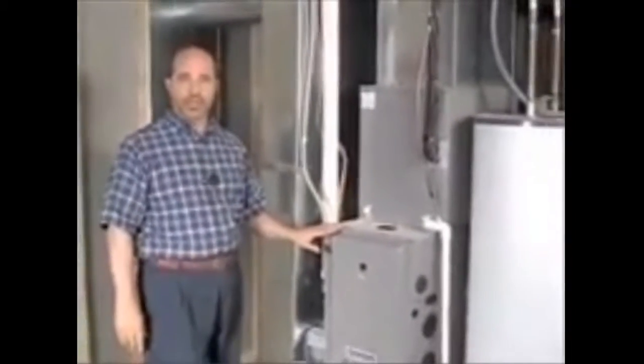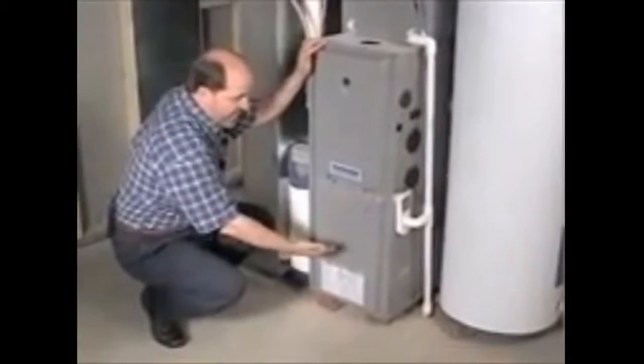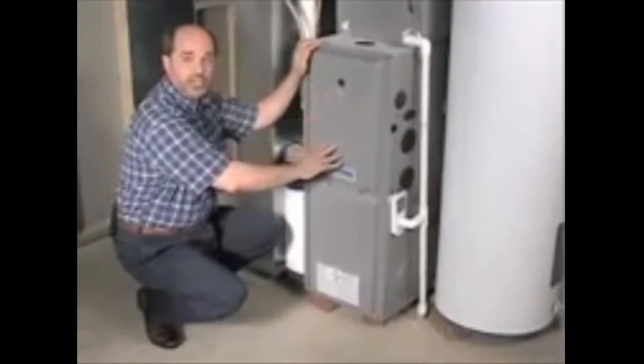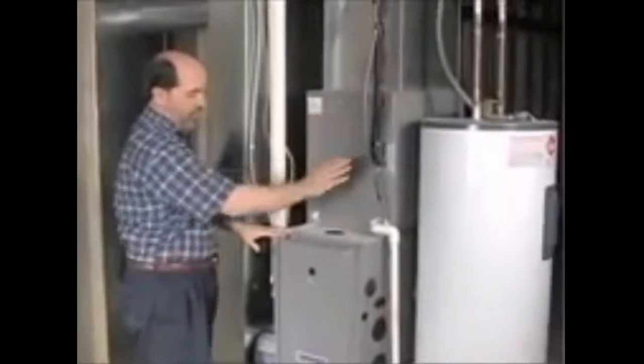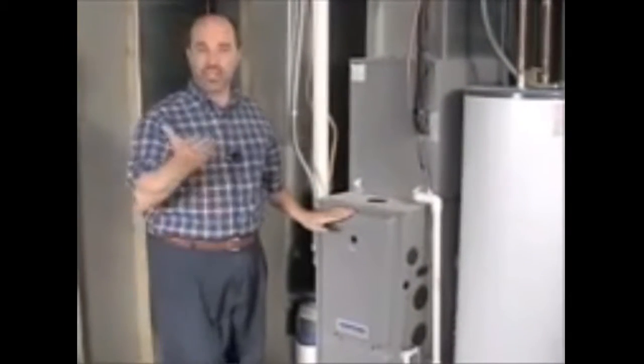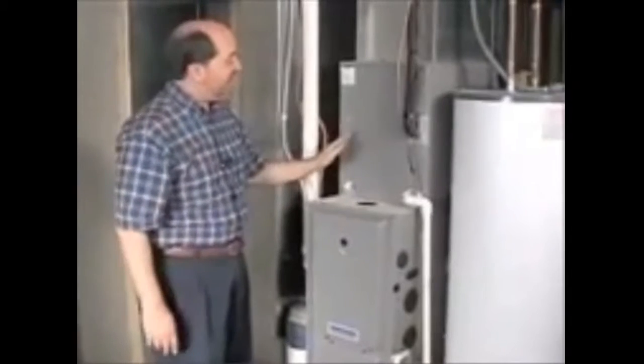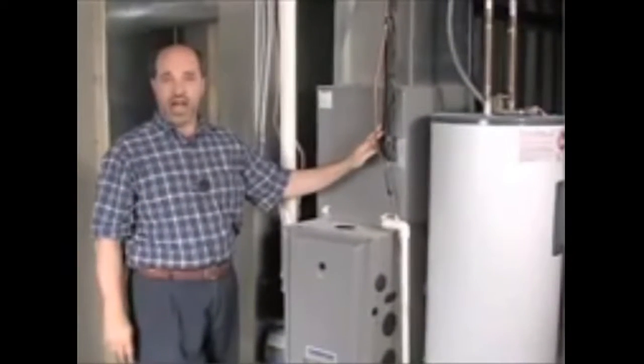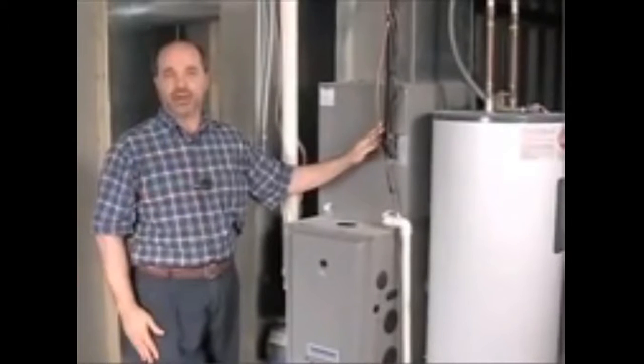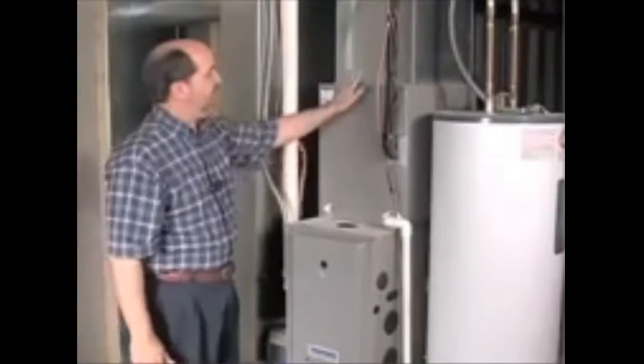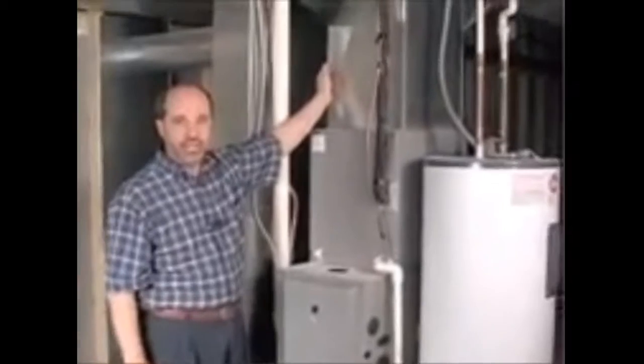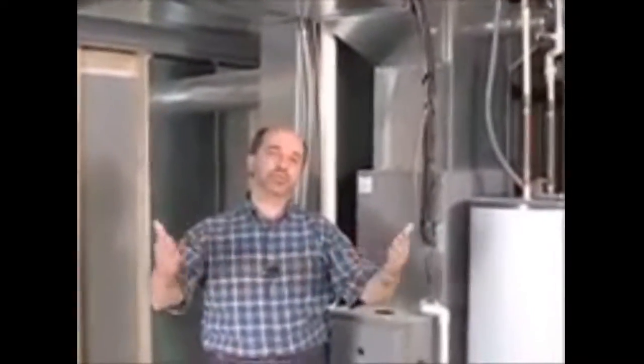We're looking at a typical upflow furnace unit that is designed with the blower fan in the lower section, bringing the air up through either the heat exchanger or the A coil. Heat exchanger, of course, raising the temperature of the air to warm your home. The A coil circulating Freon to bring the temperature down and give us air conditioning. Once the air leaves the cabinet, it goes into what we term the bonnet, which is connected then to the large trunk line, which then begins to distribute the air toward each of the individual rooms.